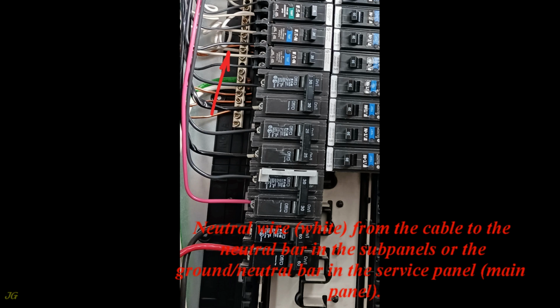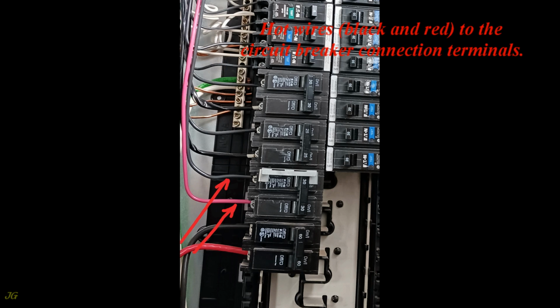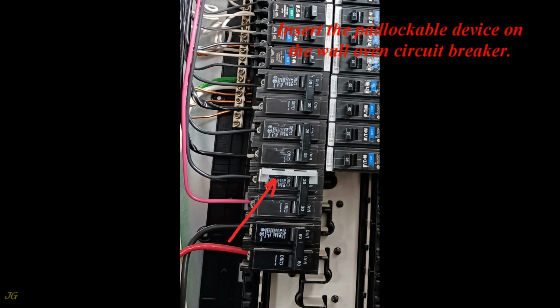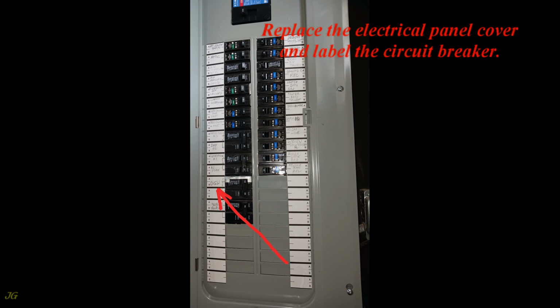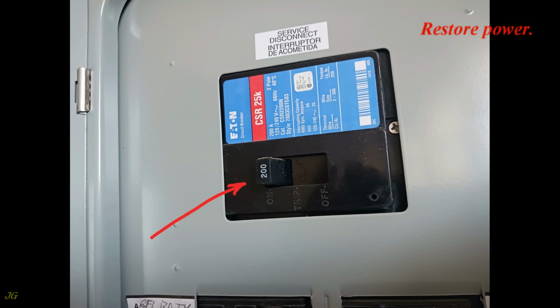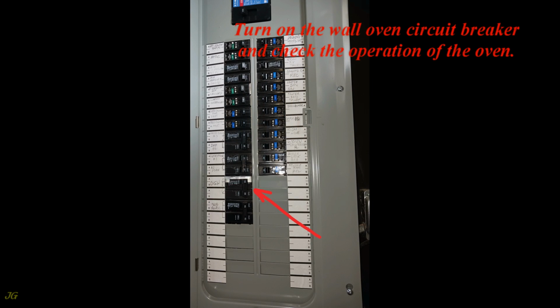Neutral wire, white, from the cable to the neutral bar in the subpanels or the ground neutral bar in the service panel, main panel. Hot wires, black and red, to the circuit breaker connection terminals. Insert the padlockable device on the wall oven circuit breaker. Replace the electrical panel cover and label the circuit breaker. Restore power. Turn on the wall oven circuit breaker and check the operation of the oven.